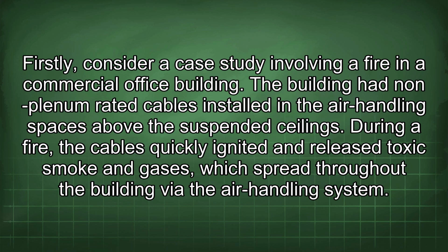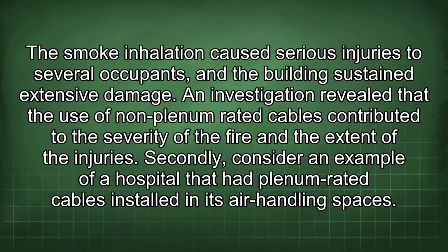Firstly, consider a case study involving a fire in a commercial office building. The building had non-plenum rated cables installed in the air handling spaces above the suspended ceilings. During a fire, the cables quickly ignited and released toxic smoke and gases, which spread throughout the building via the air handling system. The smoke inhalation caused serious injuries to several occupants, and the building sustained extensive damage. An investigation revealed that the use of non-plenum rated cables contributed to the severity of the fire and the extent of the injuries.